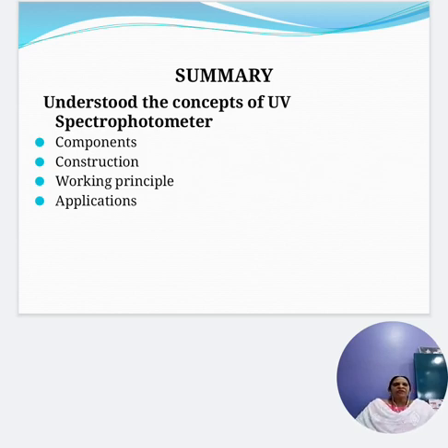We have two cells in the detector stage. Two photocells are the most commonly used for this purpose. One photocell receives the beam from the sample cell, and the second receives the beam from the reference cell. The intensity of the radiation from the reference cell is compared with that of the sample cell. This results in generating pulsating or alternating currents in the photocell.